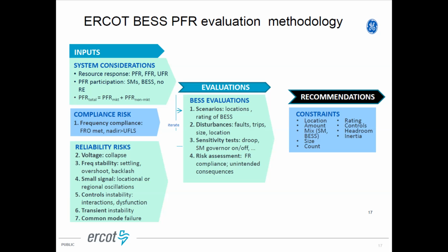As Pengwei said, the first stage UFLS acts at 59.3, and ERCOT has a practice of maintaining a 100 millihertz margin. So as we replace synchronous 5% droop machines with these fast resources: is the nadir still acceptable? Is the frequency response obligation that ERCOT has to meet still met? And is the settling frequency within an acceptable range?